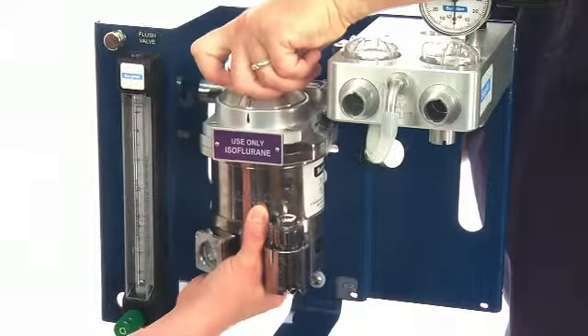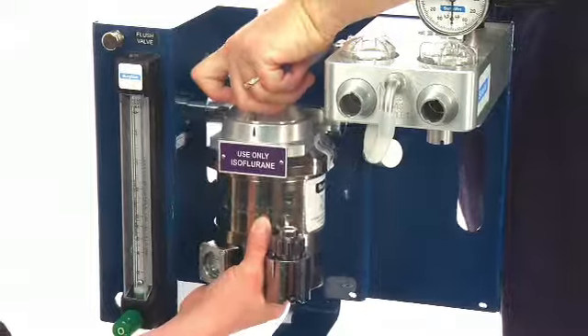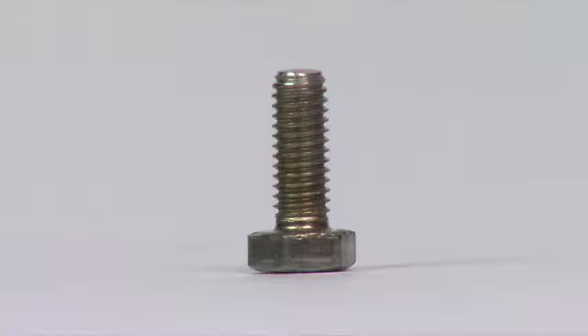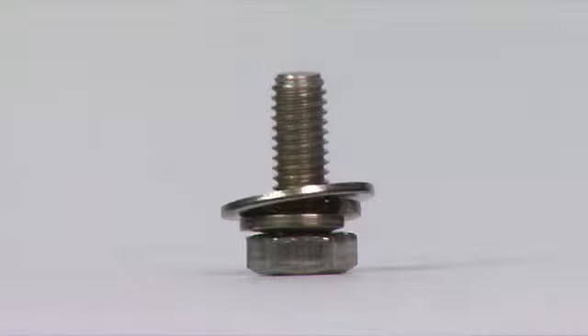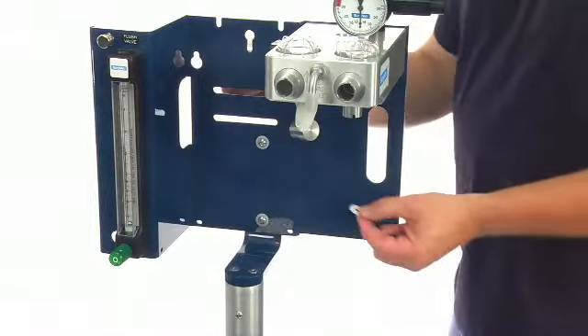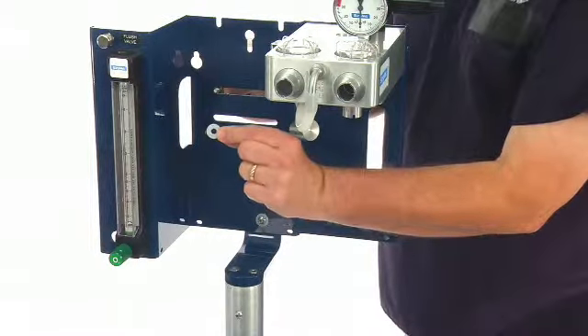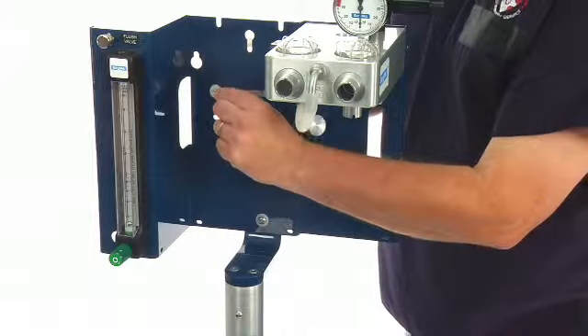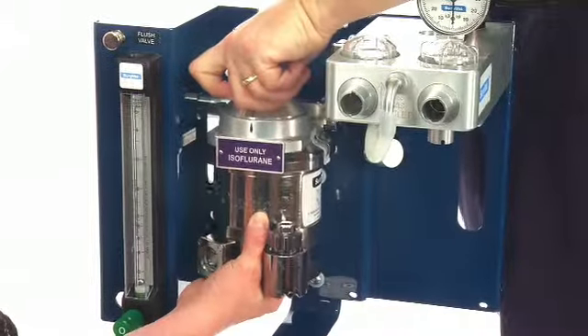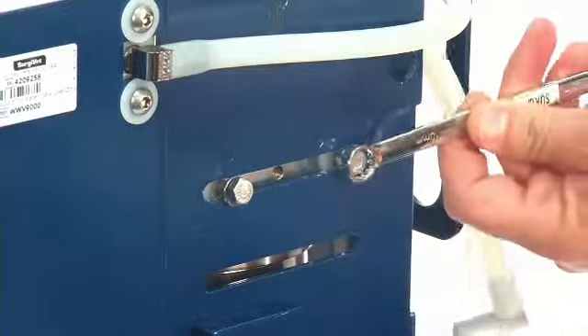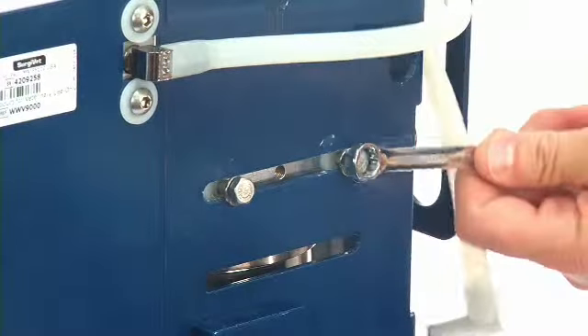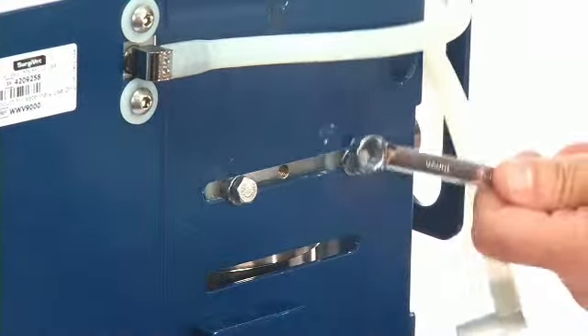It is helpful to have a second pair of hands when mounting a vaporizer. Place the locking washer, then the flat washer onto the mounting bolt. Slide the bolt through the slots on the machine and place the white nylon washer onto the bolt. Align the vaporizer with the bolts and tighten with a 10mm wrench to secure the vaporizer.